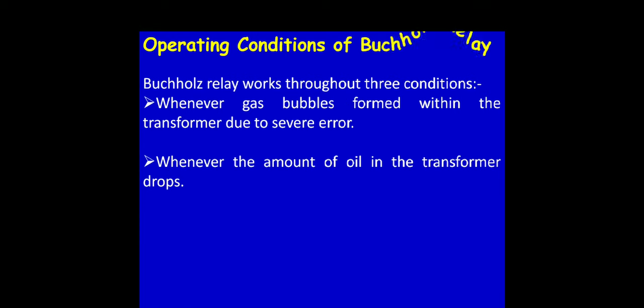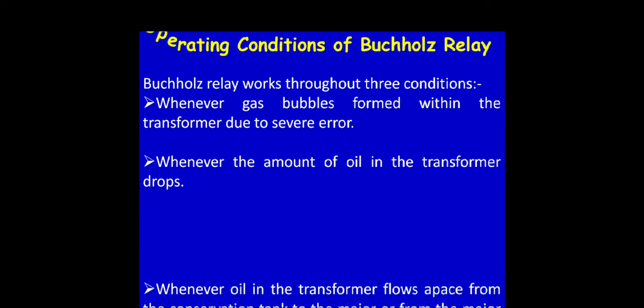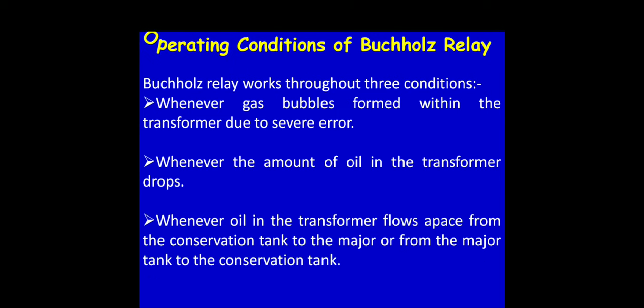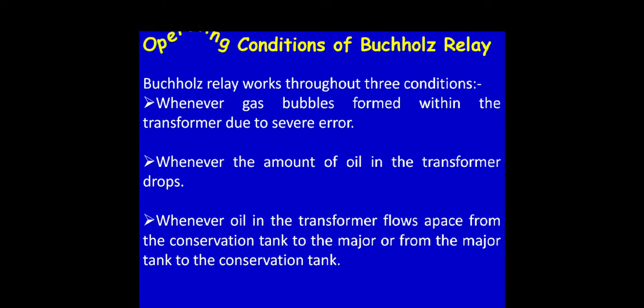The operating conditions of the Buchholz relay: the relay works under three conditions. First, whenever gas bubbles form within the transformer due to a severe error. Second, whenever the amount of oil in the transformer drops. Third, whenever oil in the transformer flows rapidly from the conservator tank to the main tank or from the main tank to the conservator tank.